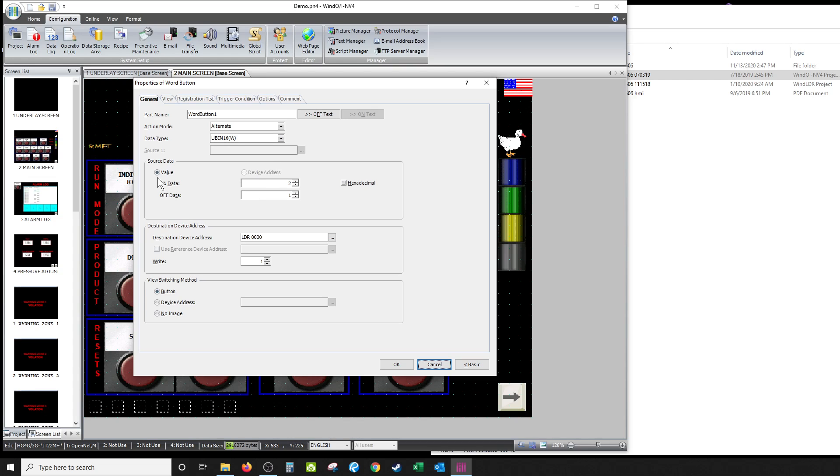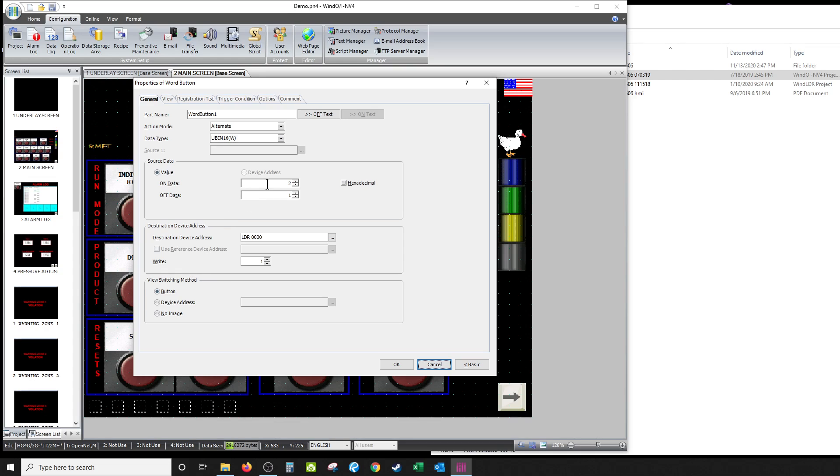Okay, so my on data is two value, and I'll show you where this is again here in a second. Off data is one. So when it's on, at LDR000, which is the actual data register within the HMI, it's going to put two in there as a binary 16-bit word. If it's off, it's going to have a one in there.